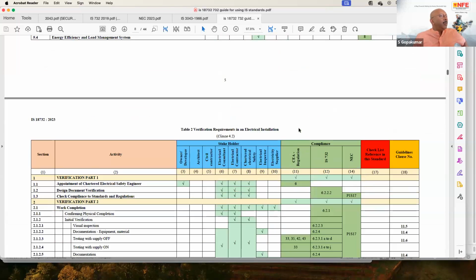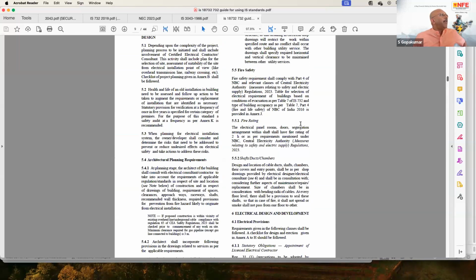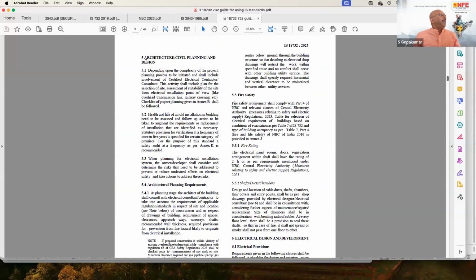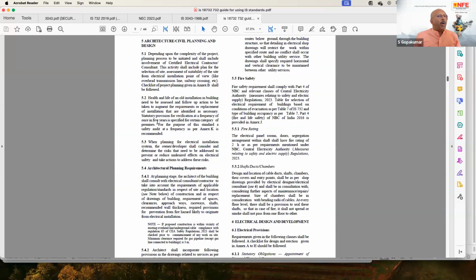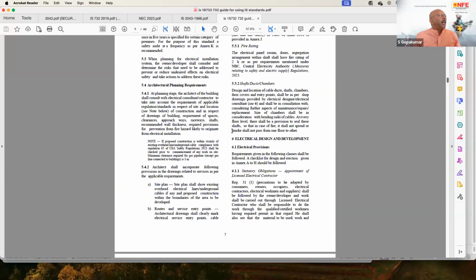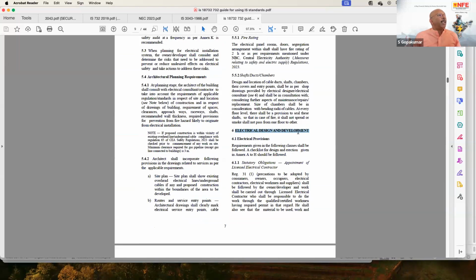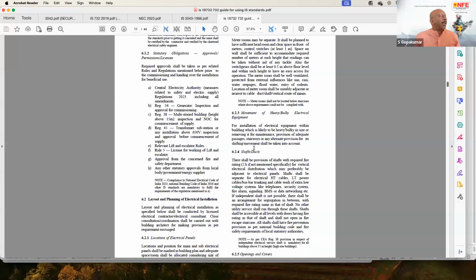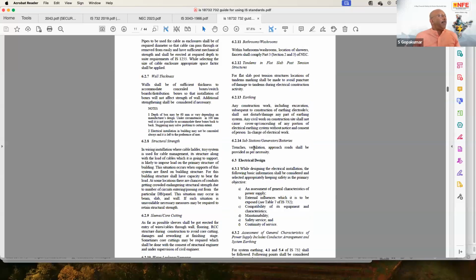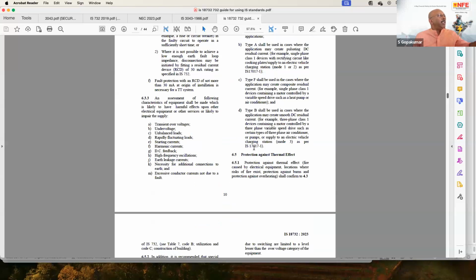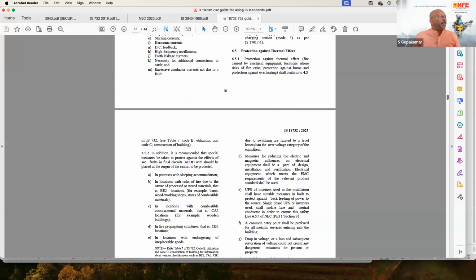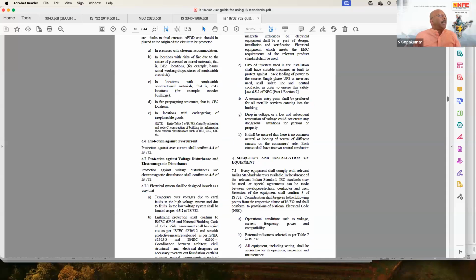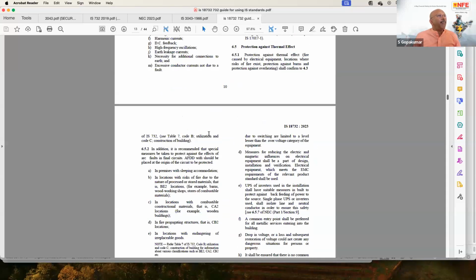Let me take you to Guidance Note 5, serial number 5. It depends on the architect, civil planning and design: what the architect should do, how he has to select. Similarly, clause 6 talks about electrical design, the things which have to be considered by the electrical consultant or the electrical designer. And clause number 7. So here all these subjects, testing, fault loop impedance and all those, are already covered. Section 7 talks about selection and installation of equipment.